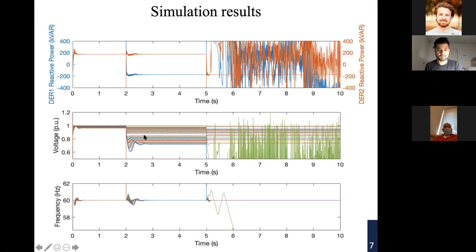So it can be inspected just by looking at it. We can see the situation gets worse and worse if the DR to APS ratio is higher, and that was our speculation in the first place, and that seems pretty obvious. Also, all these transients you see are because of the collapse. As your DR to APS ratio increases, because of this attack, the voltage and frequency just collapse if your DR ratio is very high compared to the APS. If it's small, like 1% or 2%, then it's going to sustain. Even after both attacks, nothing's going to happen. But if it goes down, it's going to be a problem.